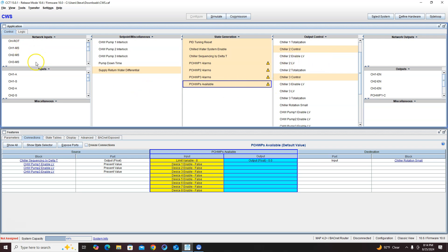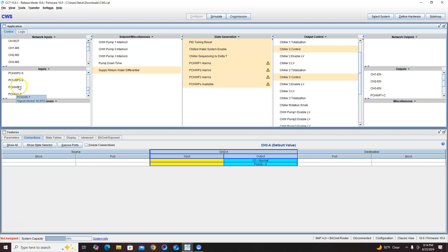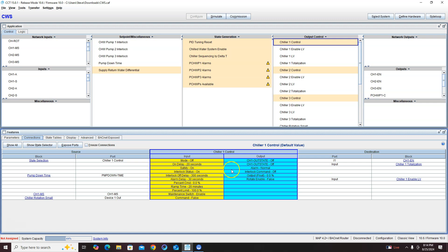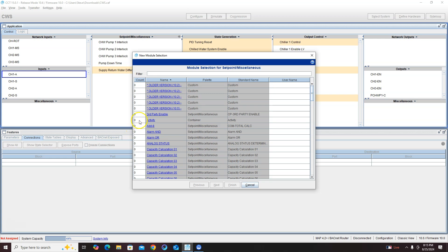To turn off one of the lead lag chillers. The alarms aren't tied to anything, I wish they were - I wish there was an option in here they would actually tie the alarms in but they don't. So you have these chill water alarms and the maintenance switches. When the maintenance switch goes disabled, it disables the chiller. So what I do with these alarms is I come in here and just create a quick activity to use these alarms to go into the maintenance switch spot.